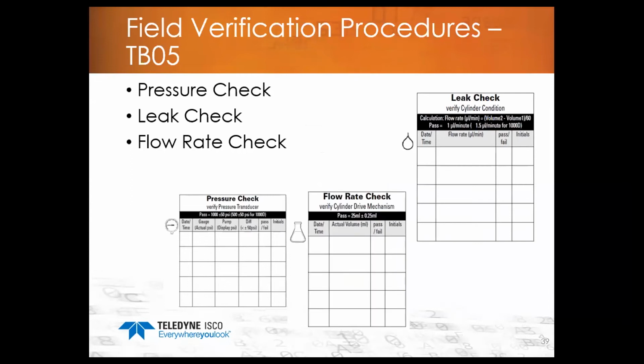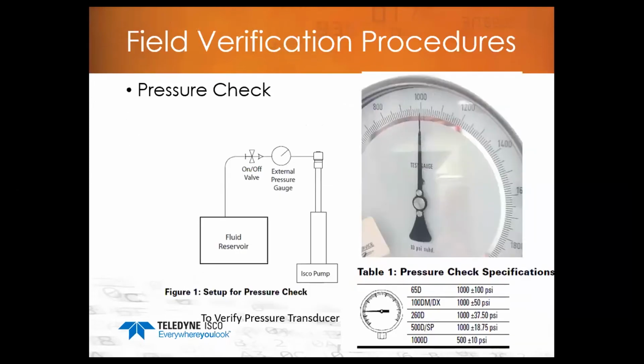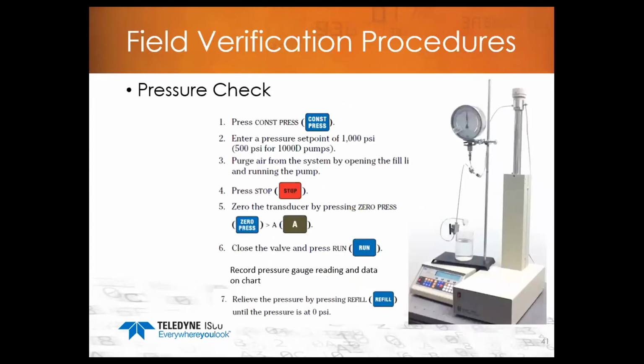We have the pressure check and the leak check, as far as field verification procedures, and that's in Technical Bulletin TB05. So on your pressure check, what you're going to want to do, I'm going to go to the next page here. You'll put the pump in the constant pressure mode, and the pressure that you'll enter first is 1,000 psi.